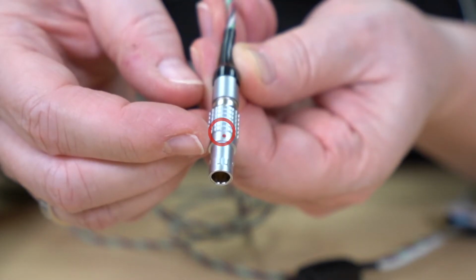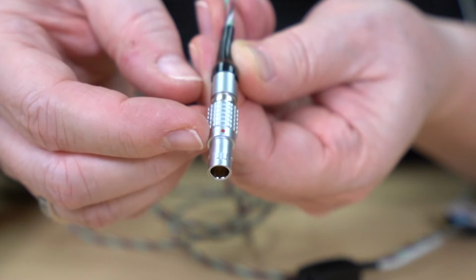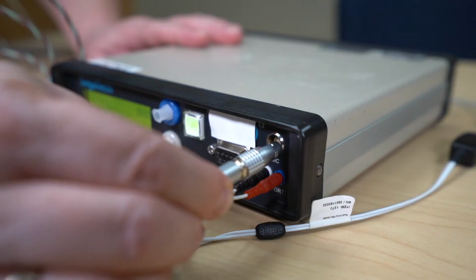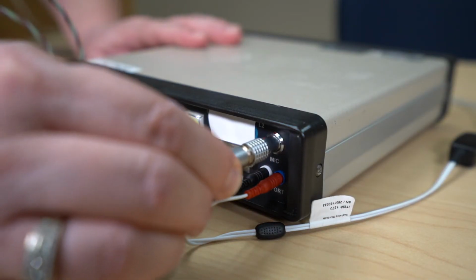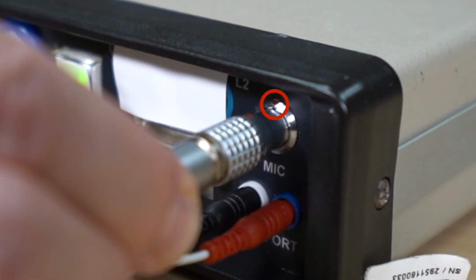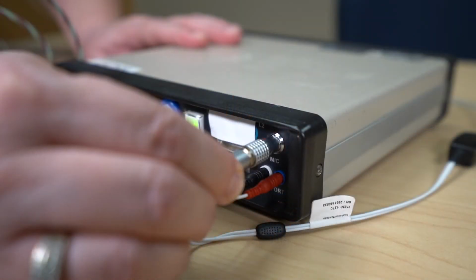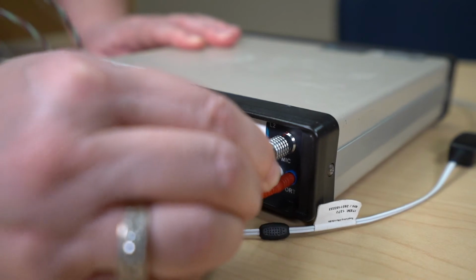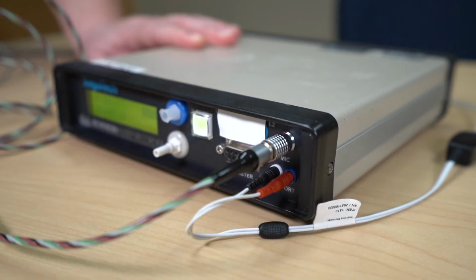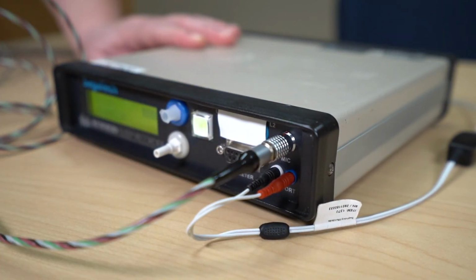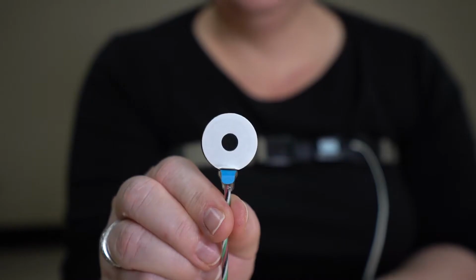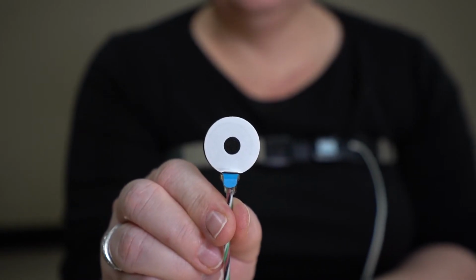You will line up the red dot or line on the connector with the red dot on the recorder in the 12 o'clock position. The connector will slide into the mic receptacle. There should be no twisting or turning of the connector. The Snore Sensor is sensing vibrations, not sound. It must be placed on soft skin at the base of your neck, not bone.